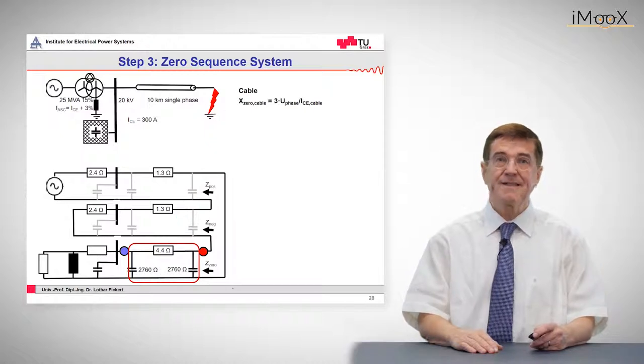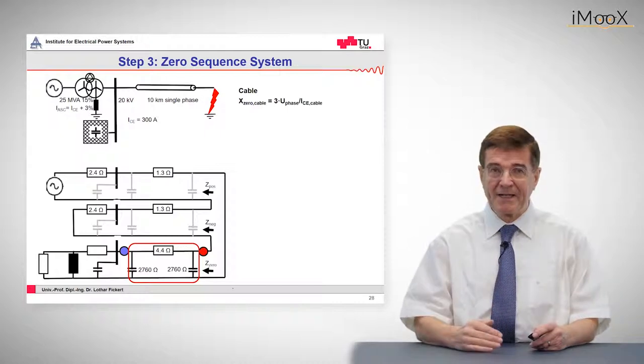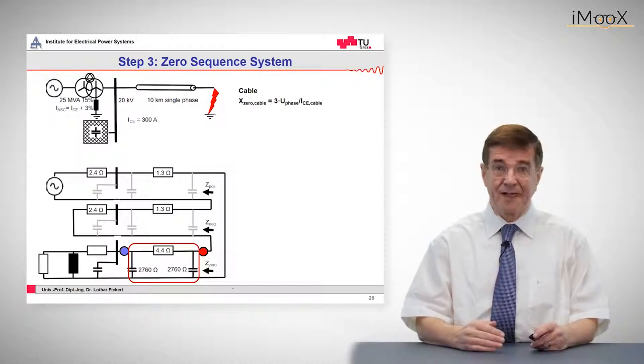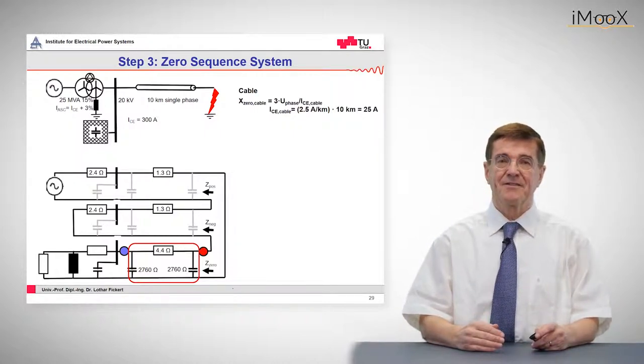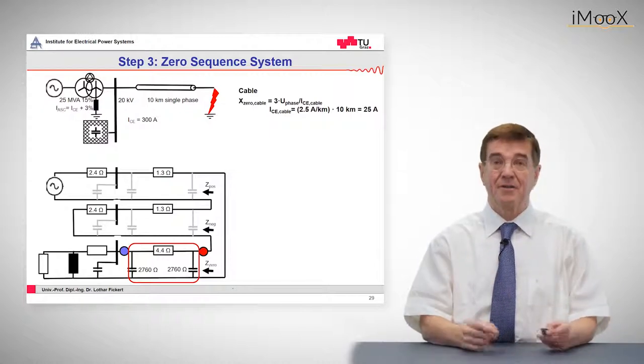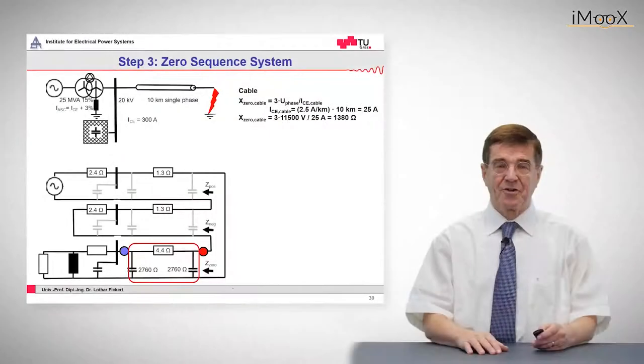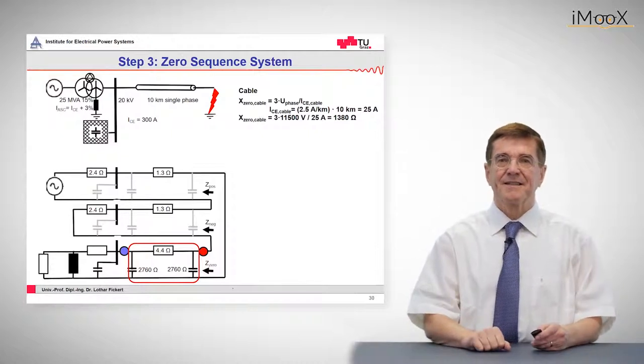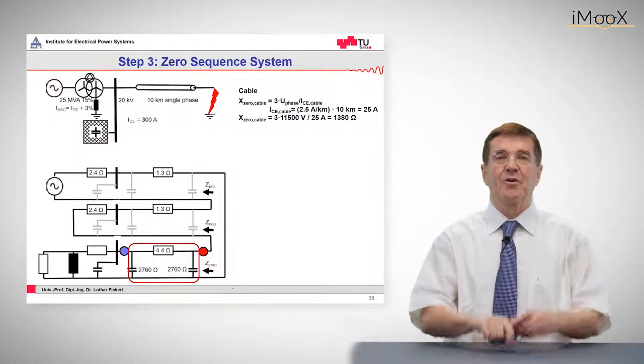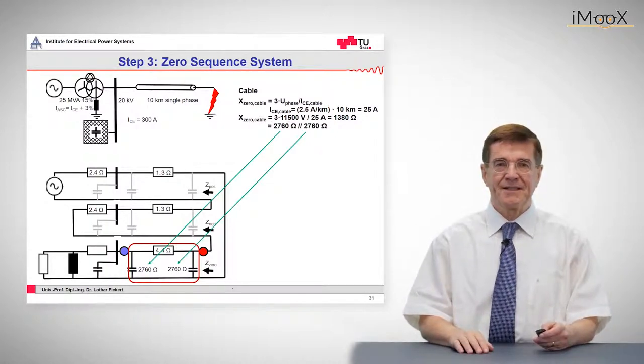But the cable also has, in this case this is important, it has transverse impedances, these capacitive reactances. And they are calculated as follows. This capacitance is given by three times phase voltage divided by the earth fault current. And then this comes out as 25 A. And accordingly the transverse, this shunt reactance is 1380 ohms, or placed on the two ends left and right of the cable, we have this value as indicated here.